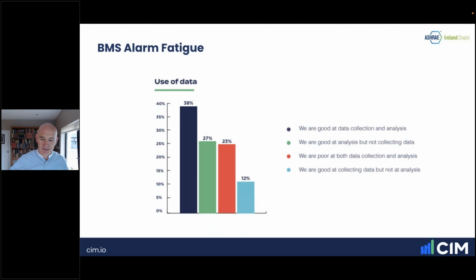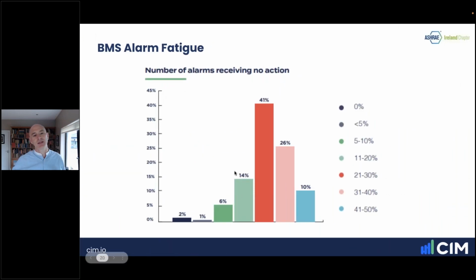The next slide goes back to the core subject of the presentation, which speaks to the number of BMS alarms receiving no action. This varied by level of alarms, with some sites getting about 30 a day, and what percentage of those were being actioned. Interestingly, about two-thirds of all respondents do get BMS alarms, but only a third of them are reacting to them, which is really interesting. The key finding from our perspective was that a lot of the issues the BMS alarm is alarming on are low and no value tasks.